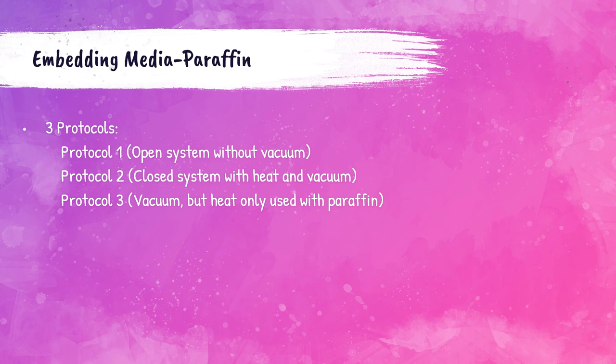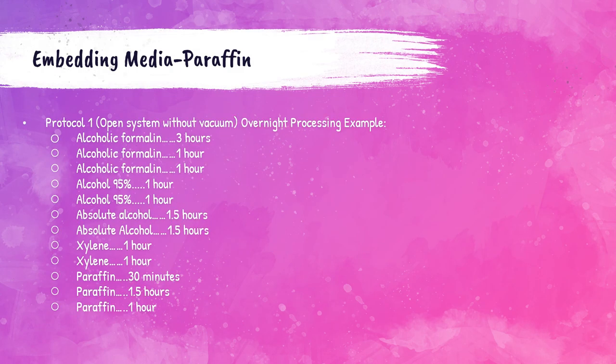There are three different protocols for paraffin embedding. Protocol one utilizes an open system without vacuum. Protocol two utilizes a closed system with both heat and vacuum. Protocol three utilizes vacuum only, with heat used only with paraffin. Here is an example of routine overnight processing utilizing protocol one — an open system without vacuum.